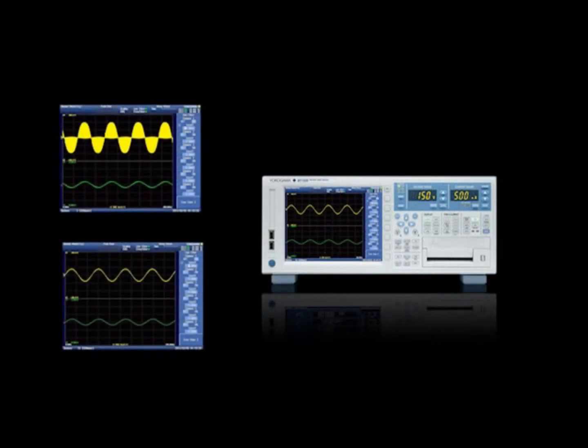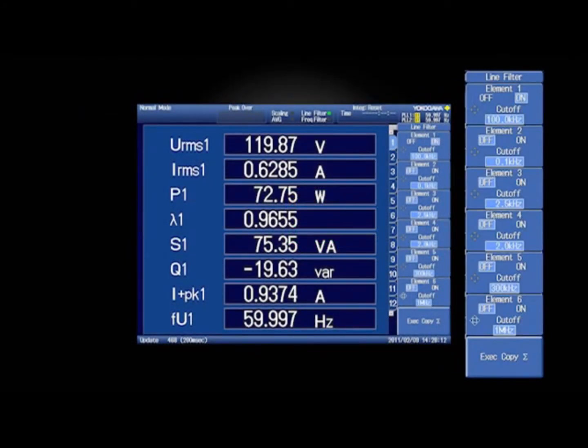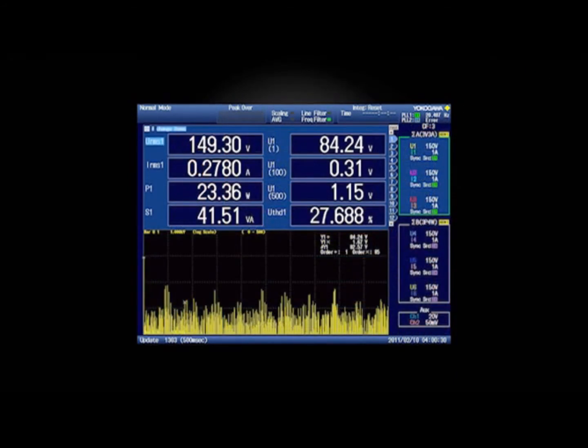A new programmable digital filter function enhances the capability to remove unnecessary harmonic components and noise superimposed on signals such as from an inverter or variable speed motor drive. This filter can be set independently for each input element, from 100 Hz to 100 kHz in 100 Hz increments. An analog filter is also provided for 300 kHz and 1 MHz filtering for each input element. Harmonic analysis can now be made up to the 500th order from a 50 or 60 Hz fundamental frequency. This is especially important in new power conversion and power electronic devices.